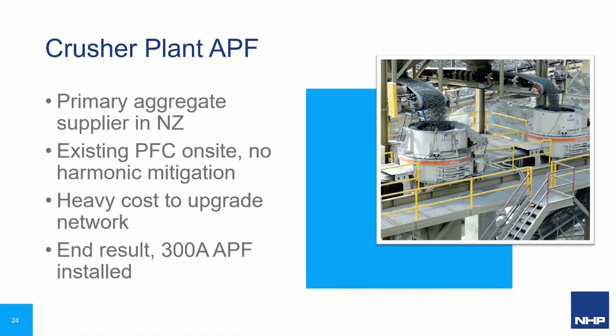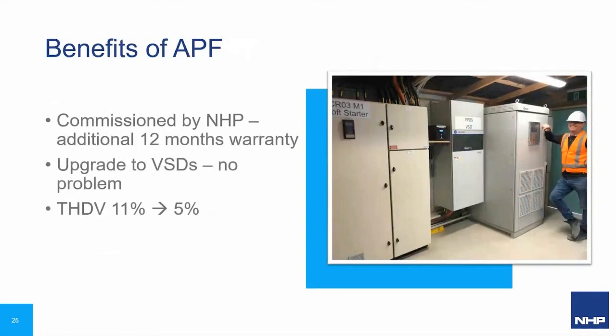Yes, of course. So NHP supplied and commissioned a Delta active power filter, or APF, and this had the effect of reducing the total harmonic voltage distortion from that 11-12% down to under 5%, typically 4 to 4.5%, with the rock crusher running at full load.